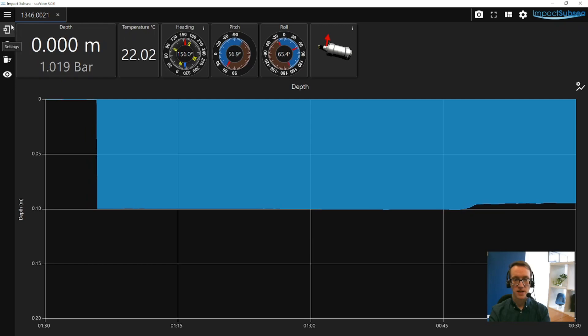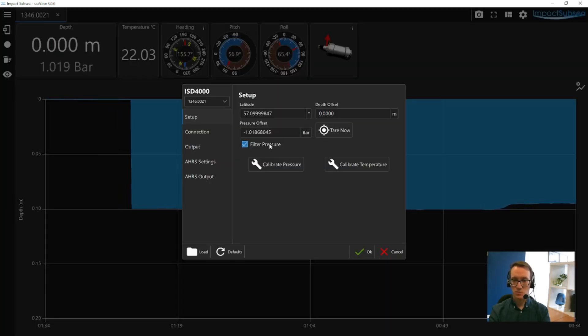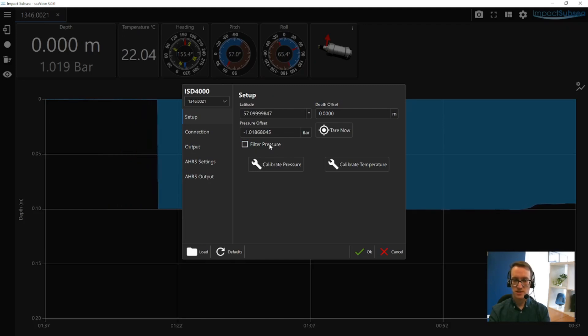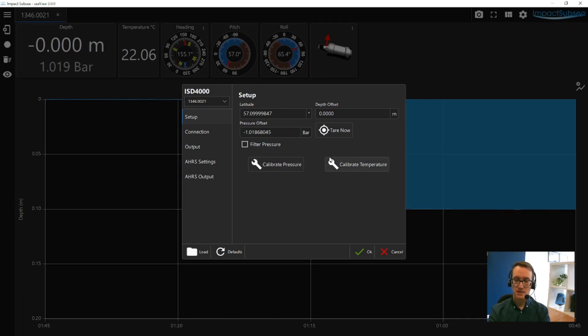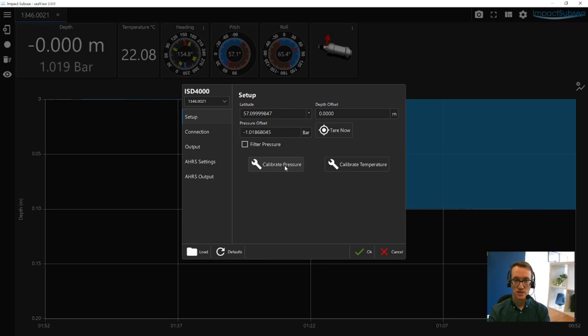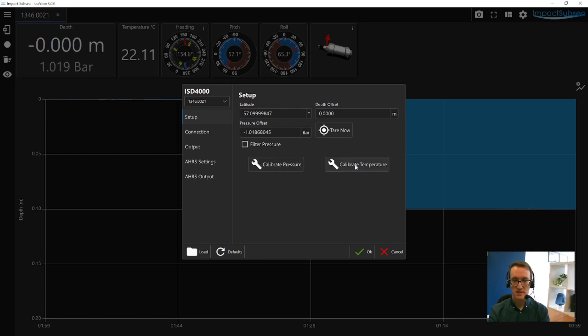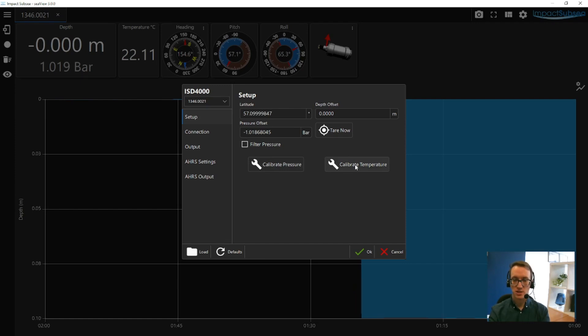If we go back into the settings again, you can also apply a filter to the pressure. So this is like an averaging filter. You can also, from this window, carry out a pressure calibration and a temperature calibration. To carry out a pressure calibration, you'll need a high accuracy atmospheric pressure sensor, combined with a deadweight tester and associated weights. And for the temperature calibration, you'll need a number of temperature baths, each at a set temperature.